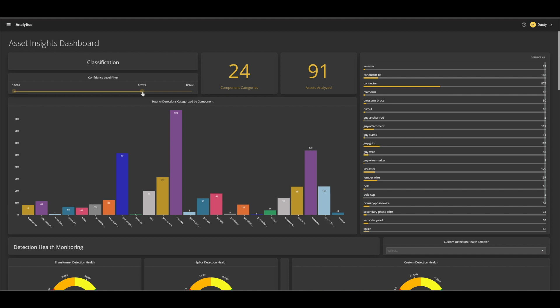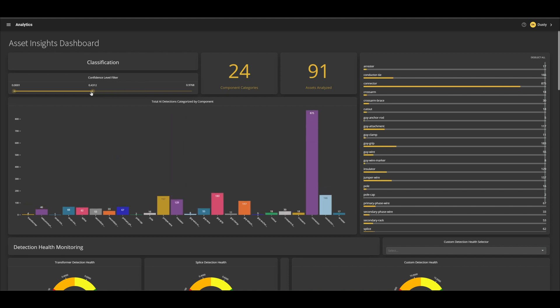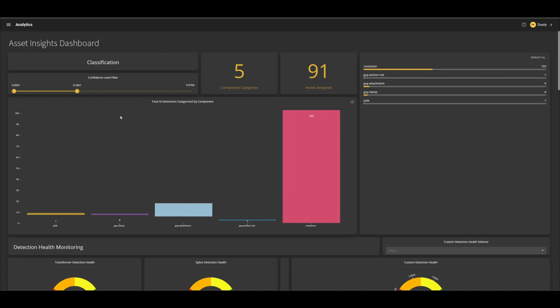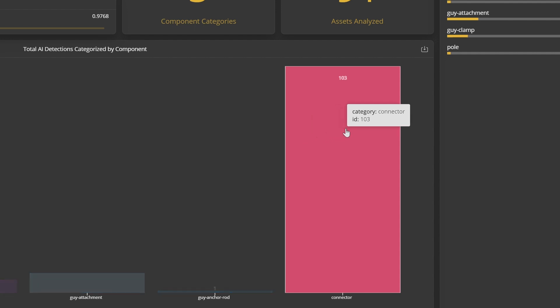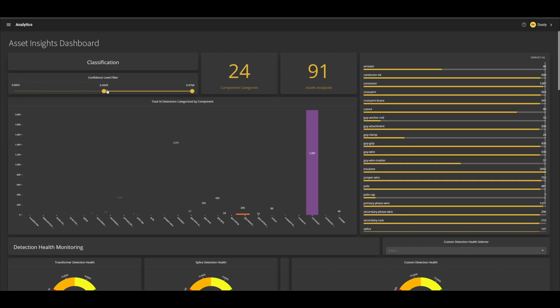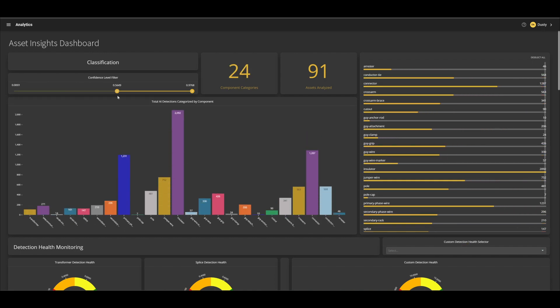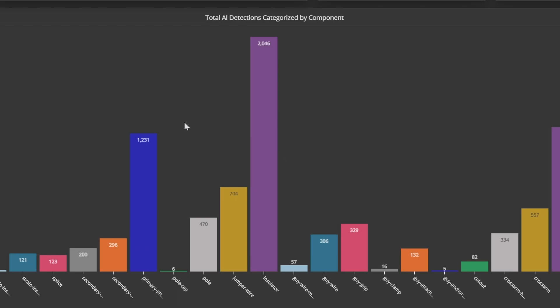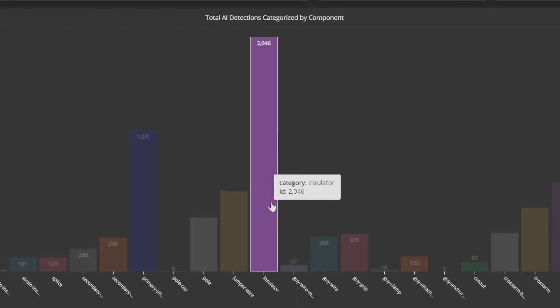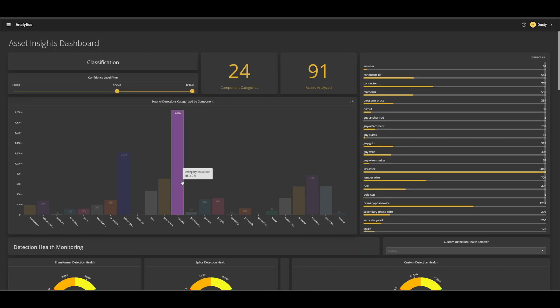We can adjust these things to add levels of granularity for building reports and making informed decisions. For example, we can look at the component histogram for instances of components that the model reports having the lowest detection confidence. We can immediately see that the connector component is highly represented in the lower confidence scores and may require more training, additional data, or expanded parameters to increase confidence in the results. We can also look at the components that the model has the most confidence in and see that insulators and primary phase wires are doing quite well.